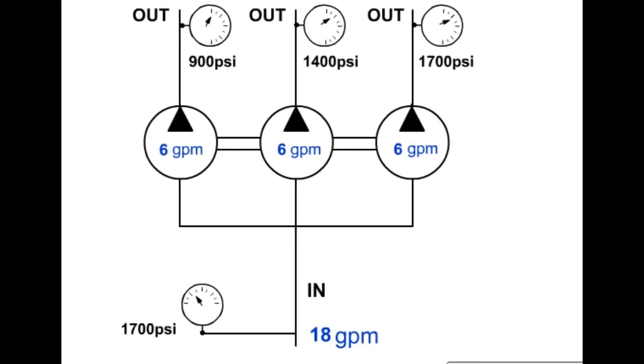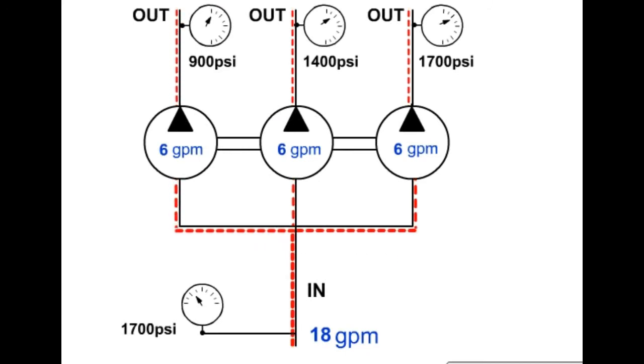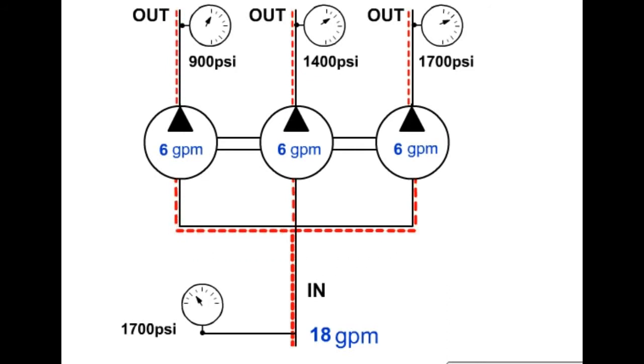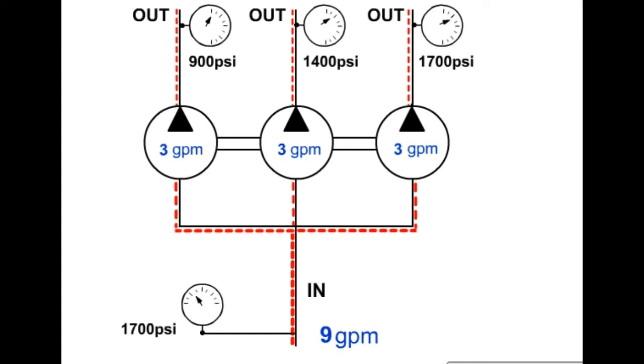The gear-type proportional divider can divide the flow into two or more flow paths. The positive displacement of the gear sections produces a constant division of the flow, even if the loads and pressures in the output circuits vary. The output flows are proportional to the input; as the input varies, the output flows will vary proportionally.